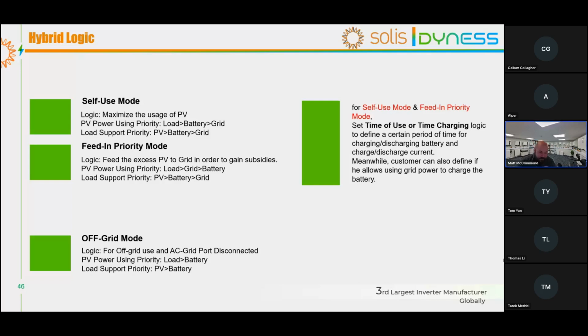Feed-in priority is the other mode, but that's only really used in countries where the price paid for energy export is higher than the cost of storing it. It means your inverter just works like a normal grid-tied inverter, where it never stores energy in the battery. It will always supply the load, then export all available energy to the grid. That means when you're using a battery system in that mode, it has to have time of use. So the country might have an Economy 7 tariff, but they still want to export through the day. Then they can do this, and your battery only works by time-of-use charging, so it will only charge based on a window you select. We'll talk about time of use because it's quite important.